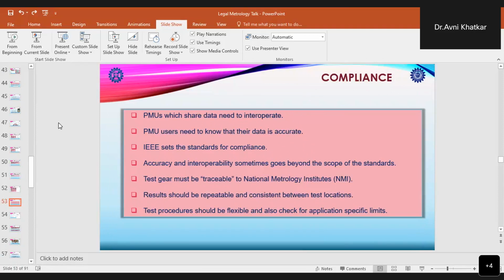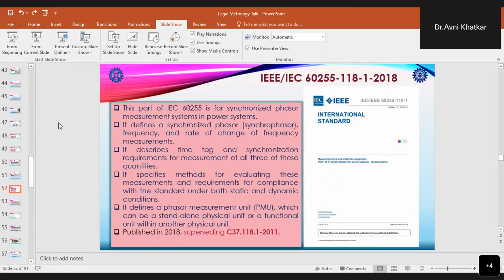And in this 2018 standard, the frequency error and rate of change of frequency error, that is FE and RFE, are expressed as signed values compared to the absolute values in the previous standards. These signed values of errors are very helpful, as they provide the grounds as well as the nature of the error. Keeping all this in mind, this has been changed in this standard.